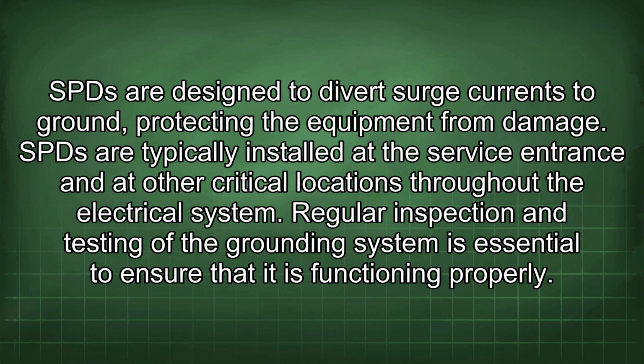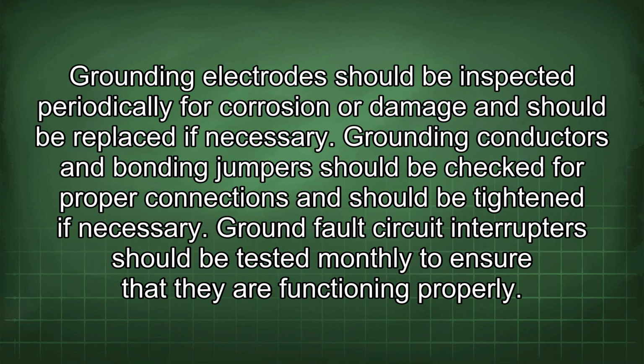Regular inspection and testing of the grounding system is essential to ensure that it is functioning properly. Grounding electrodes should be inspected periodically for corrosion or damage and should be replaced if necessary. Grounding conductors and bonding jumpers should be checked for proper connections and should be tightened if necessary. Ground fault circuit interrupters should be tested monthly to ensure that they are functioning properly.